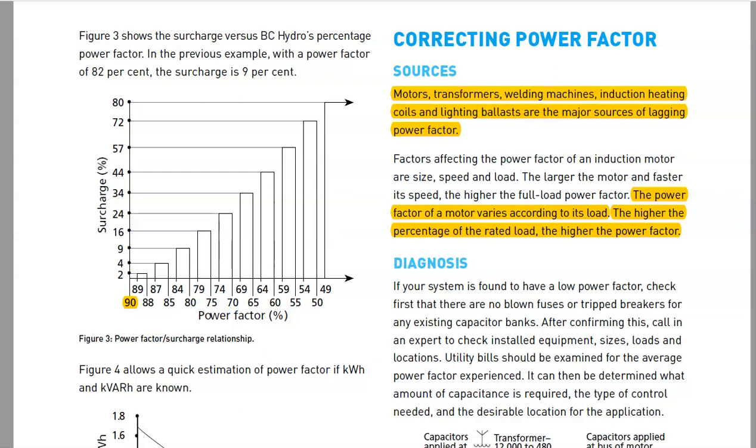And you figure that they're going to need a 10 horse motor, but you happen to have a 20 horse sitting around, don't sell them the 20 horse. Because they should be using that 10 horse. The 10 horse is going to be utilized to its maximum. Otherwise, you're magnetizing for 20 horse, but you're only delivering 10 horse, which means you're going to have a wicked low power factor from that motor. So you want to try and use your motors as close to the line as possible.